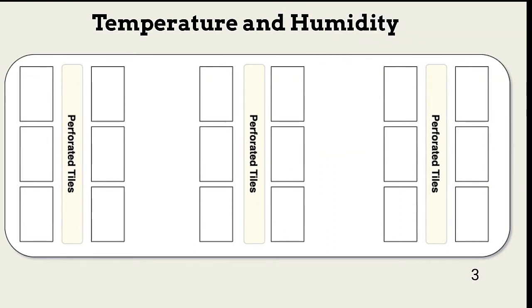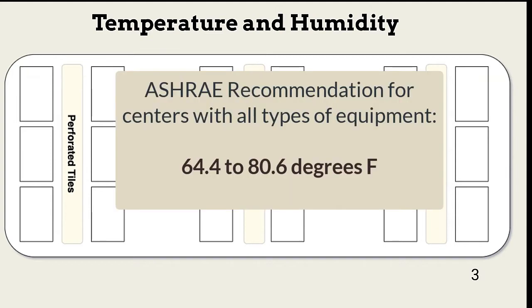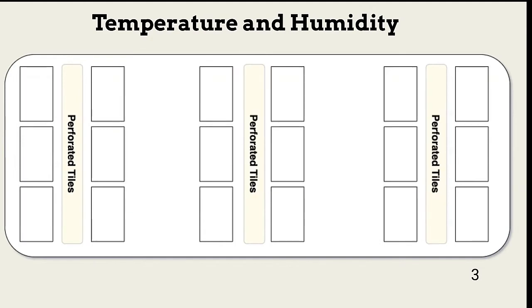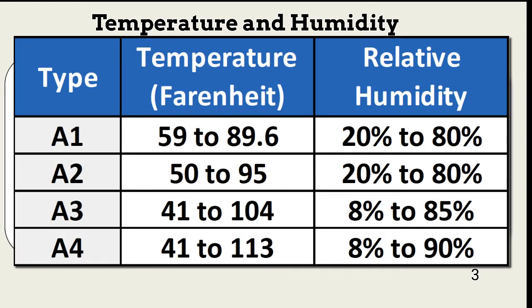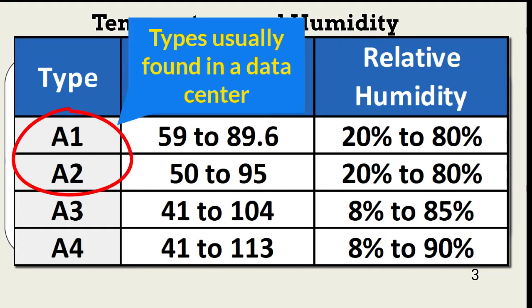There are various temperature and humidity recommendations based on the type of equipment protected and its criticality. The American Society of Heating, Refrigerating, and Air Conditioning Engineers, or ASHRAE, recommends keeping data centers between 64.4 to 80.6 degrees Fahrenheit to address temperature requirements for all types of equipment. The table shown depicts the equipment types and the temperature and humidity requirements for each.